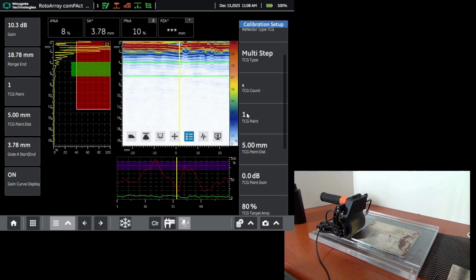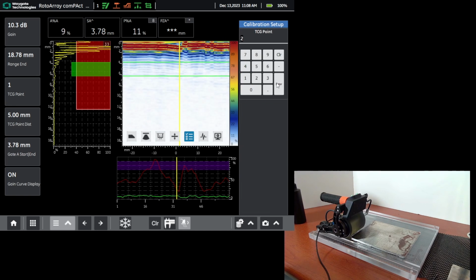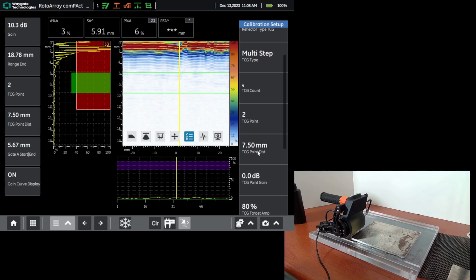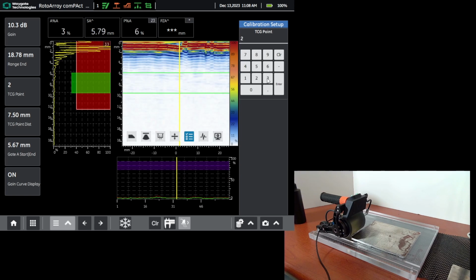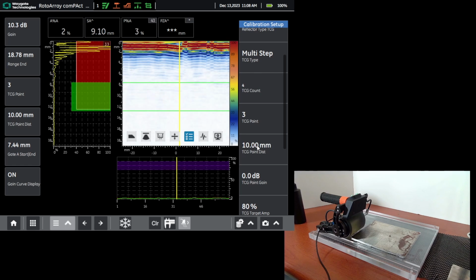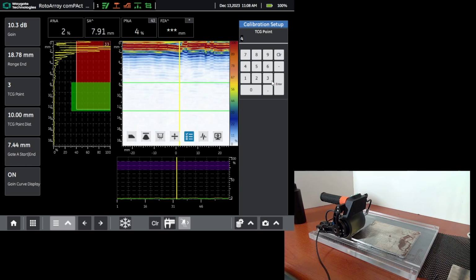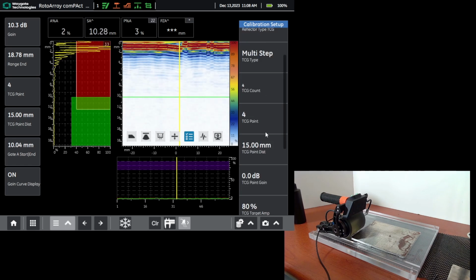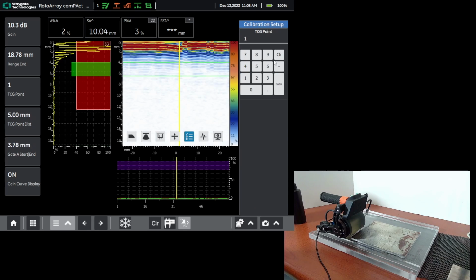our calibration. Then we'll select our first point, and I've already told it that the first point is going to be at 5 millimeters thickness. Go to our second point. Second point is going to be at 7.5. The third point, 10 millimeters, and the fourth point will be at 15 millimeters thickness. So I've told it where to expect during the calibration, the depths to expect for the steps that we're going to look at. Put that back to point 1.